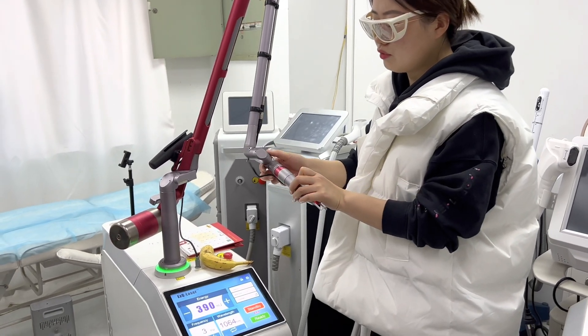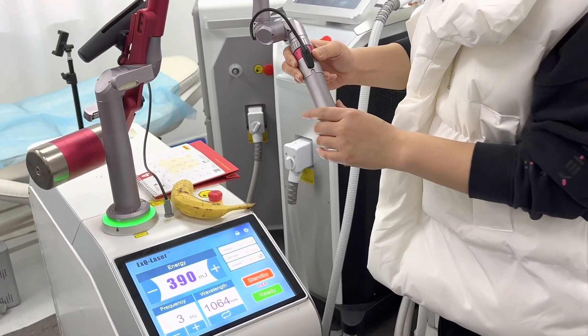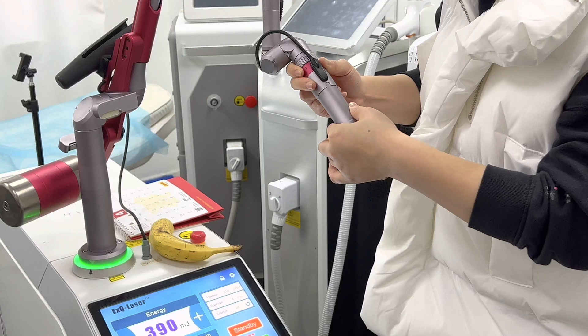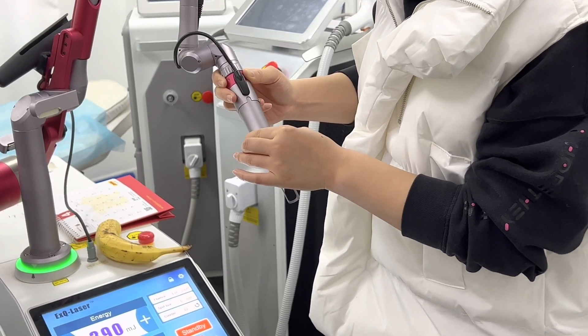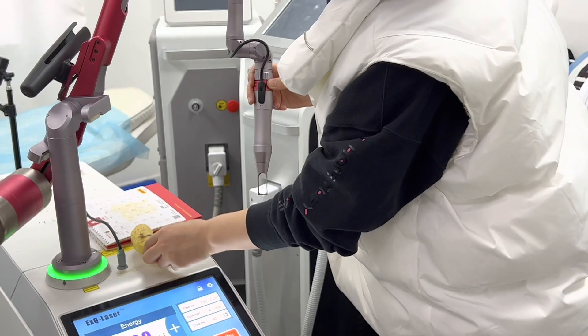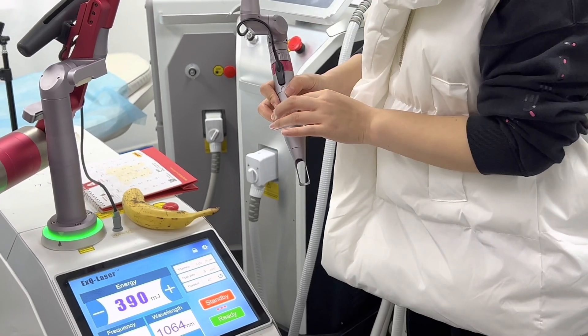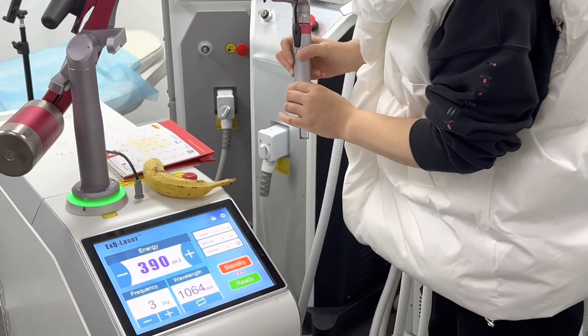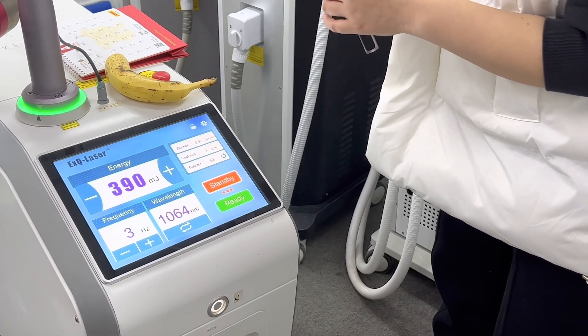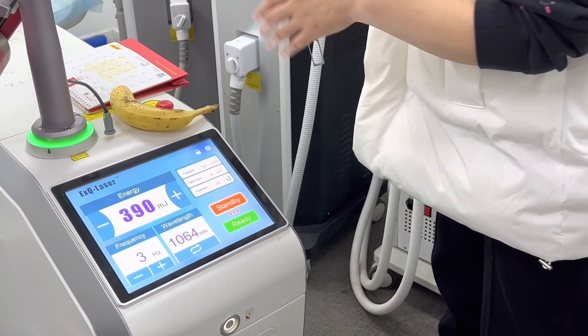It's easy and flexible to move over the whole treatment area. To adjust the spot size, press in and just twist it to whichever size you want. Because the spot size on this pigmentation is not too big, we can choose 3 to 5 mm. A smaller spot size gives you higher fluence. You can see that when I adjust the spot size, the fluence is also changed.